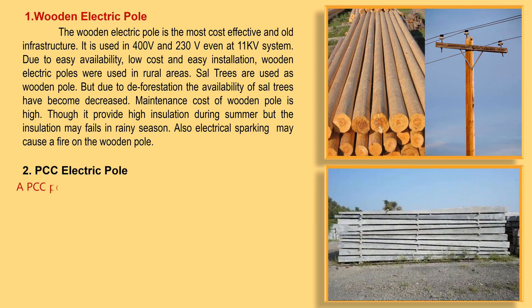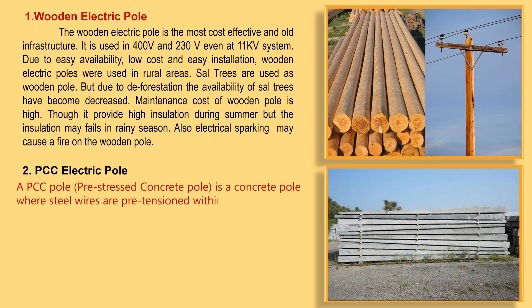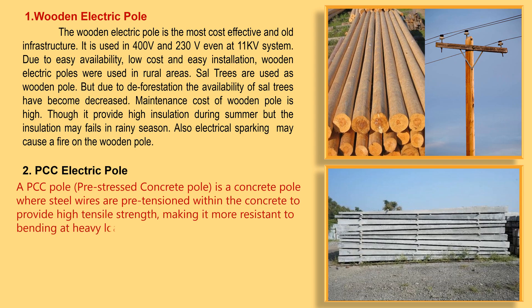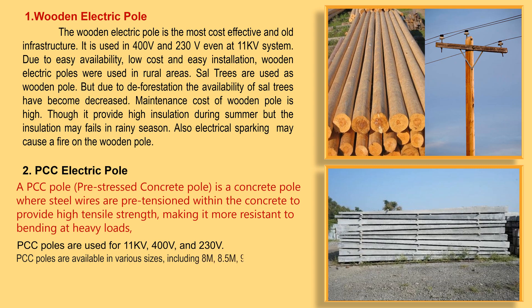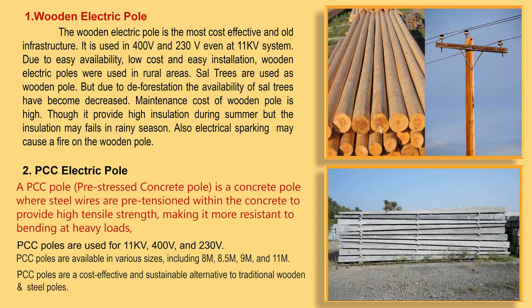A PCC pole — pre-stressed cement concrete pole — is a concrete pole where steel wires are pre-tensioned. It provides high tensile strength within the concrete, making it more resistant to bending at heavy loads. PCC poles are used for 11kV, 400V, and 230V systems, and are available in various sizes: 8 meter, 8.5 meter, 9 meter, and 11 meter. PCC poles are a cost-effective and sustainable alternative to traditional wooden and steel poles.